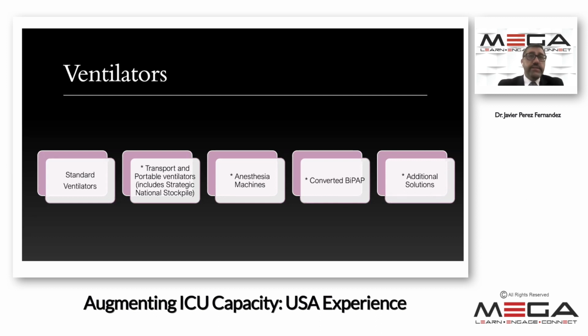We also converted non-invasive ventilator equipment for use in the ICU. But remember, the BiPAPs you convert into ventilators are not volume cycled, they're pressure cycled and pressure limited, so it becomes a bit of a challenge. It's not as simple as connecting someone to an invasive ventilator using a BiPAP and leaving them alone. Disasters happen frequently because of that, so it requires different attention.